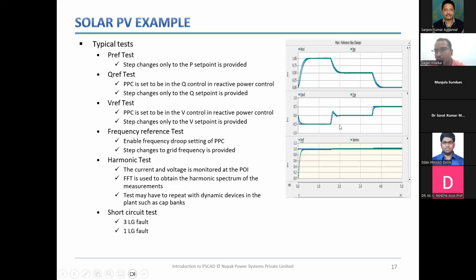In this case, you can see that it matches. It ultimately achieves the set point which is provided, but it may not do so depending on the control philosophy or any parametric changes, the PI controller values, the dead band, the ramp rate control. This is especially important since your inverter will be manufactured by someone else, your PPC will be manufactured by someone else, and then the plant is operated by someone else. So, all these things should work together to achieve the desired output.